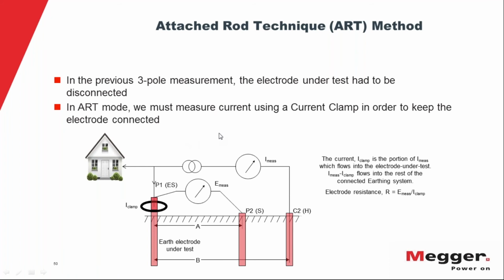So in the old days, you used to have to break the utility connection, which is not easy and not a good idea in many instances. But now with ART method, you get a special tester that has a built-in current clamp. And you clamp that around either your ground rod or your grounding conductor, but you clamp it downstream of your alligator clip. And now this is going to measure how much of your test current returns by your own on-site ground. And that's where it's going to base its measurement. And it's going to ignore what goes back through your utility ground that you don't care about. So that's your ART method, and that's a good way to be able to test grounds that are already installed, but you don't want to lift them.